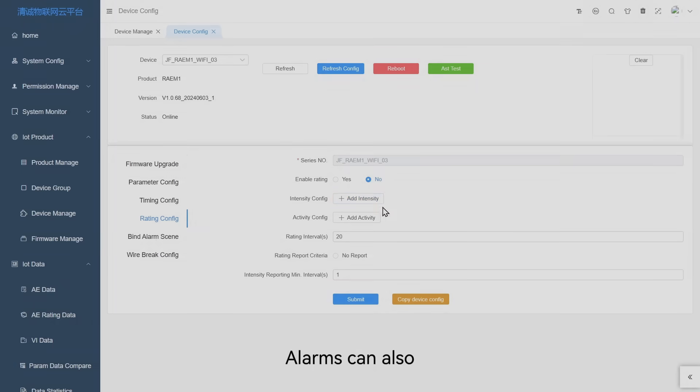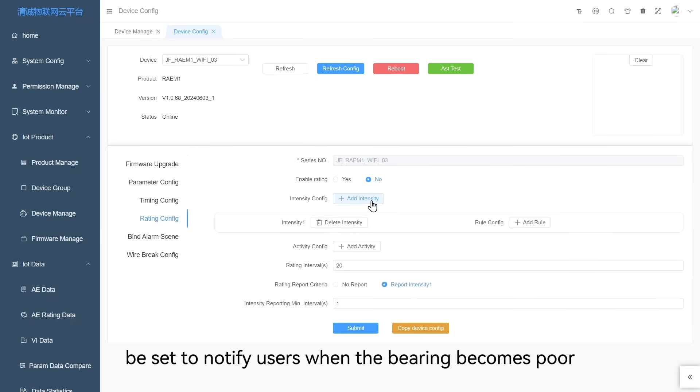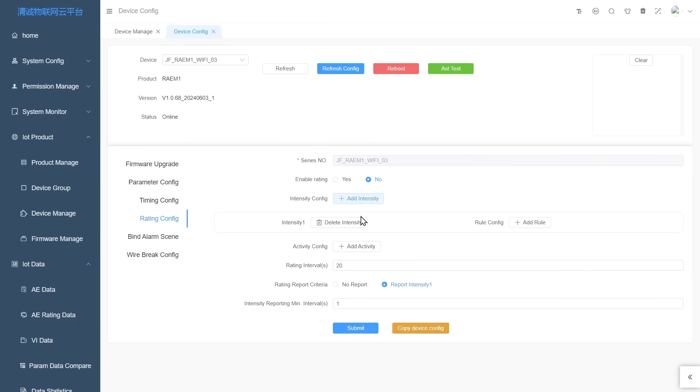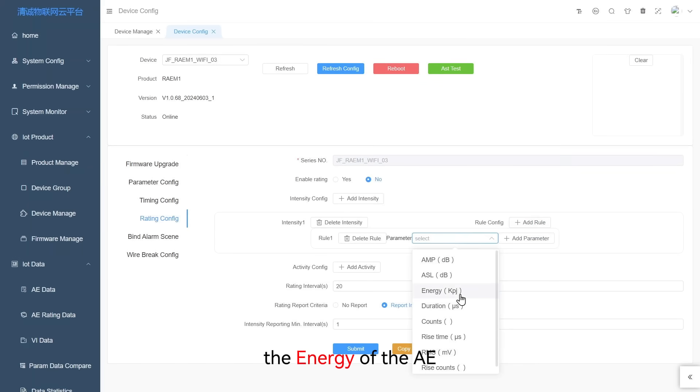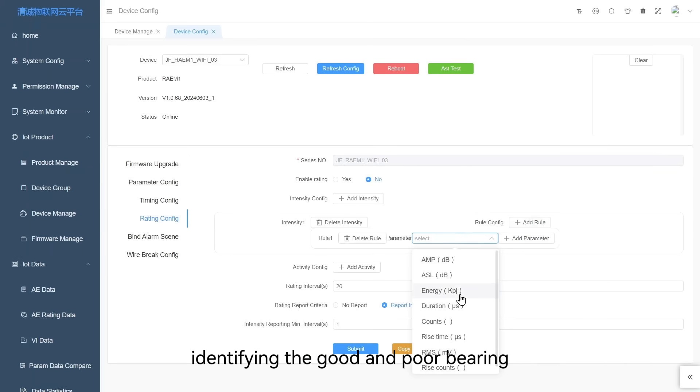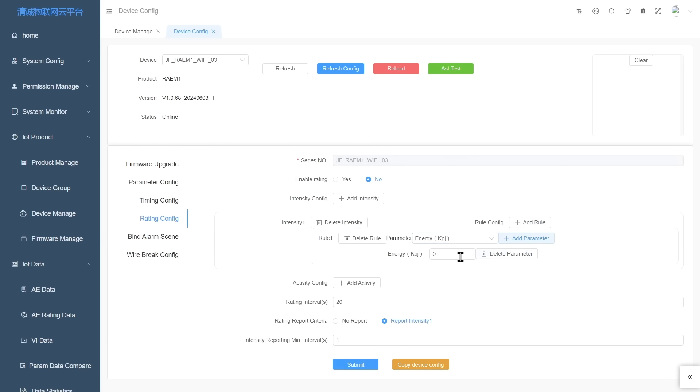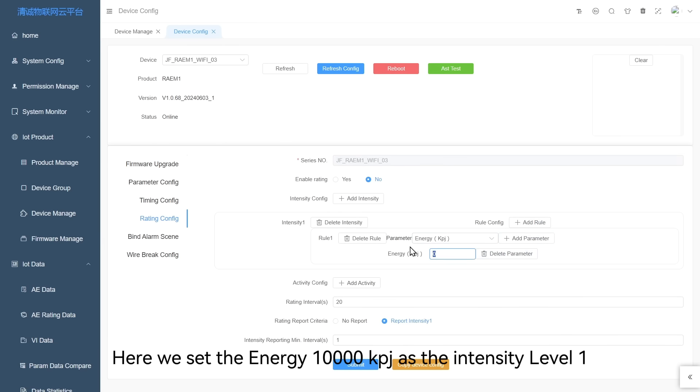Alarms can also be set to notify users when the bearing becomes poor. Based on the parameter correlation graphs, the energy of the AE signal can be used as the defect criteria for identifying good and poor bearings.